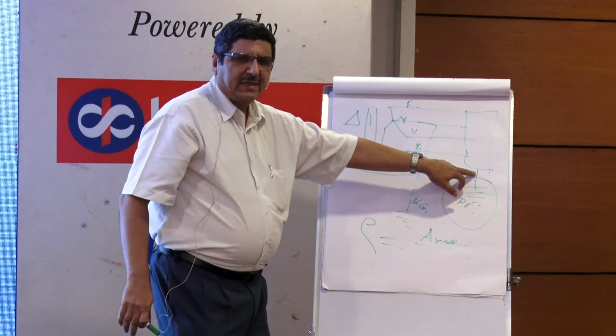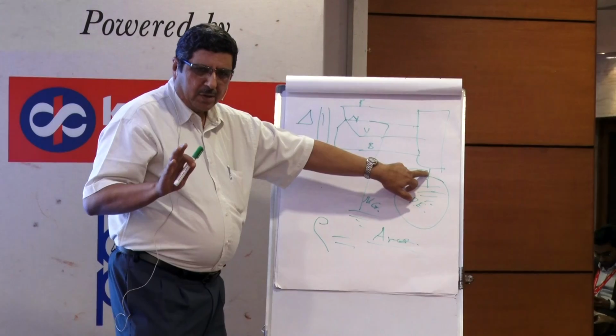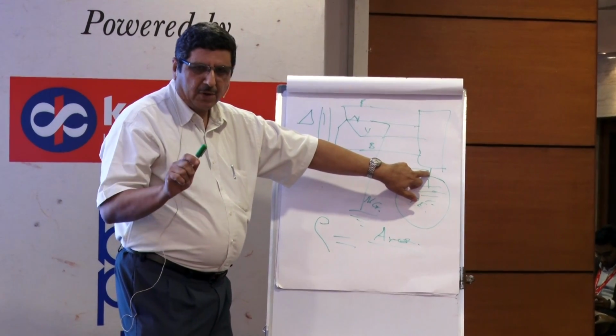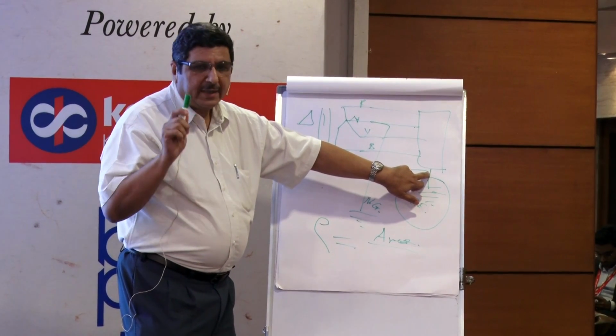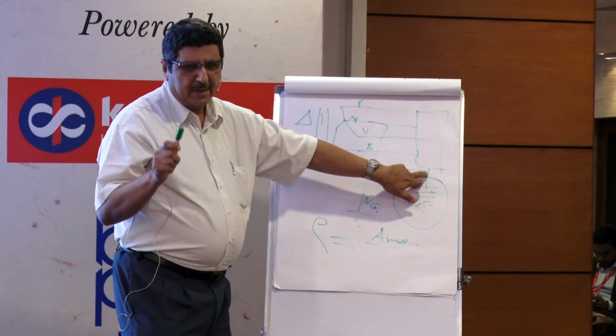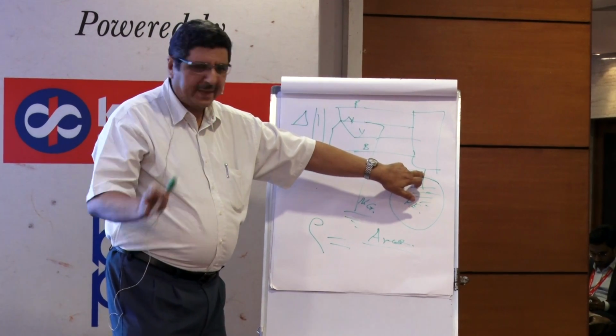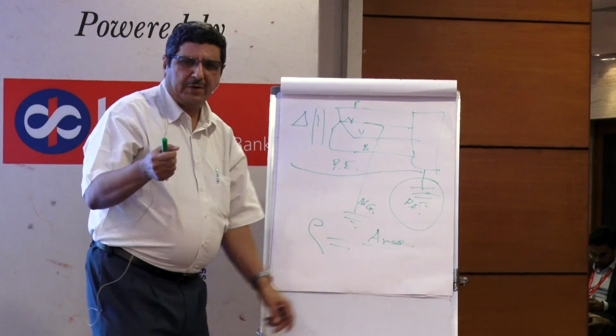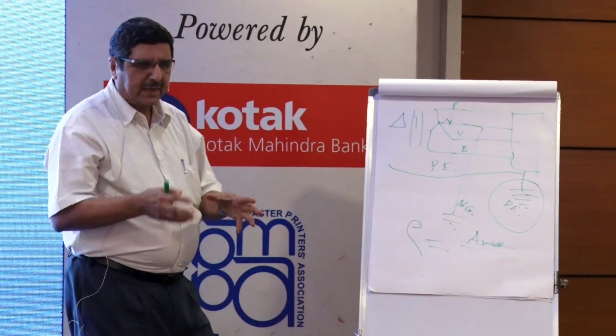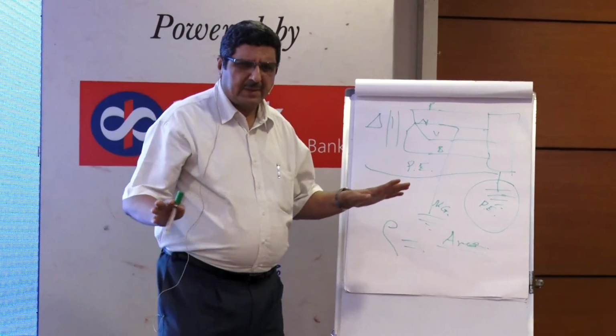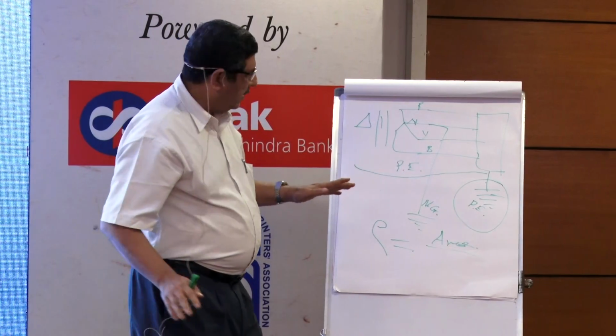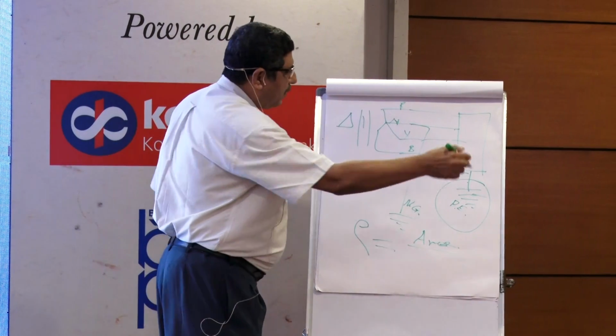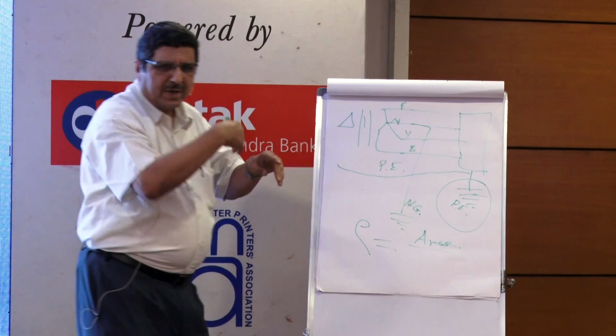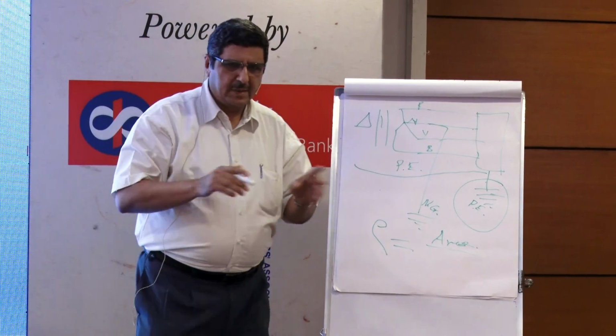nobody should say that only copper is to be used. You can use galvanized iron strips, pure galvanized iron with good micron percentage coating, hot dip. Hot dip is the main word. If it is cold dip, it is just painted. So hot dip, if you use 40 by 5 or 30 by 6 or something like that, it is very cheap compared to copper, and it is very secure. The moment you bring that strip from the grounding to your factory, the job is done.